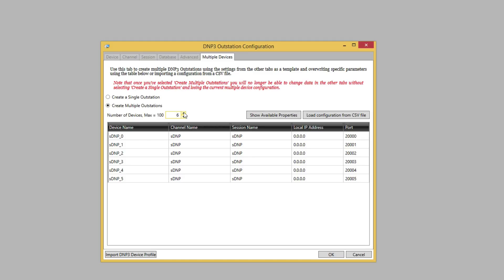Here we could change the device name or other information. Note that by default, the devices start with the port specified on the Channel tab, in this case, the DNP3 default port of 20,000, and increment for each device. We'll just use the defaults for this demo, so we could select OK.